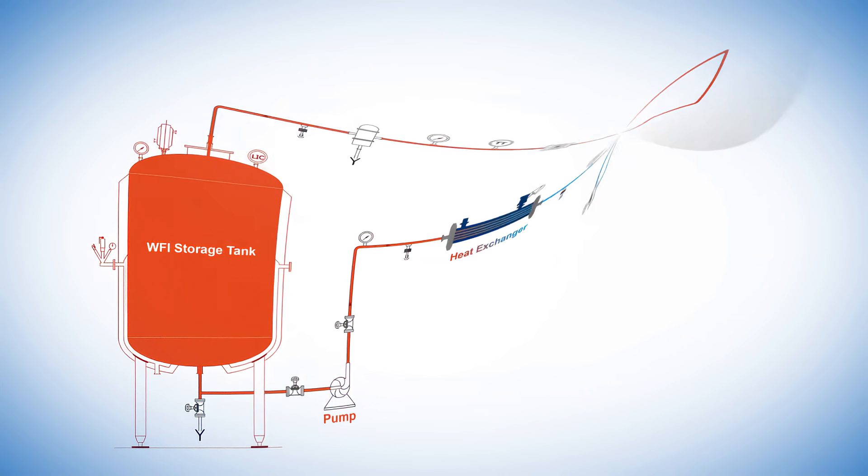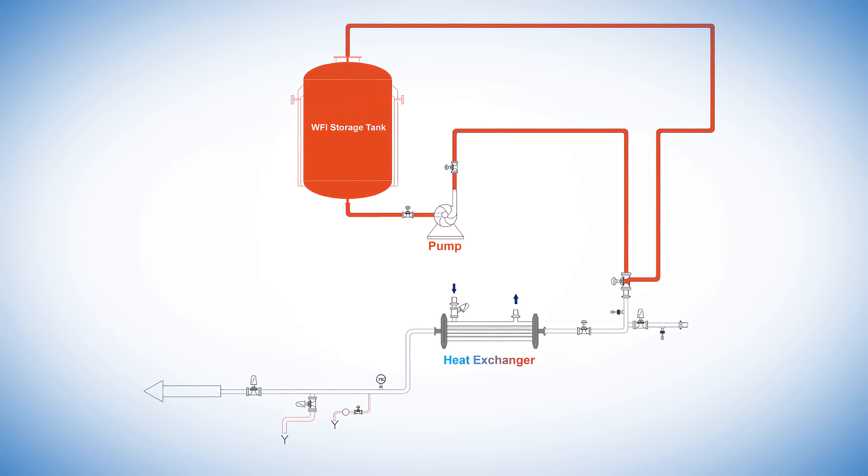Another method uses a valve and heat exchanger mounted on a T in the WFI loop. When the valve is opened, the water is cooled through the heat exchanger at the point of use. Using this method, the heat exchanger needs to be sanitized prior to each use.